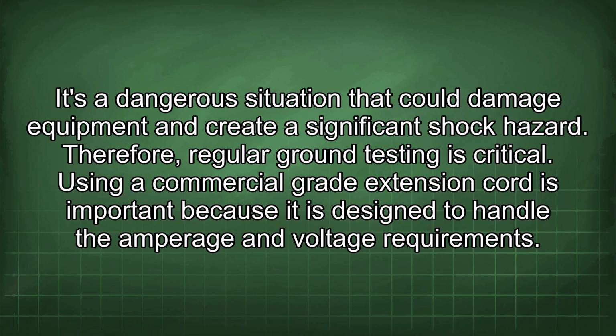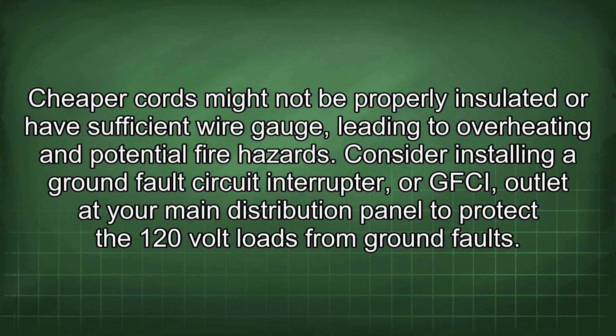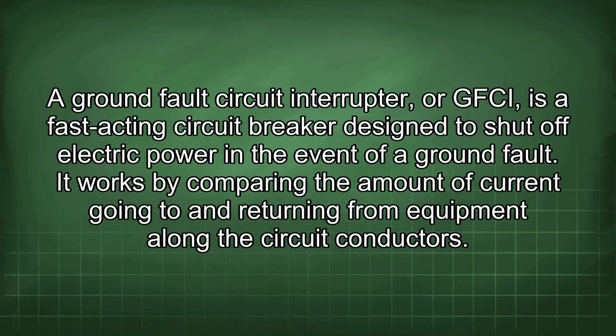Using a commercial-grade extension cord is important because it is designed to handle the amperage and voltage requirements. Cheaper cords might not be properly insulated or have sufficient wire gauge, leading to overheating and potential fire hazards. Consider installing a ground fault circuit interrupter or GFCI outlet at your main distribution panel to protect the 120-volt loads from ground faults. A GFCI is a fast-acting circuit breaker designed to shut off electric power in the event of a ground fault.